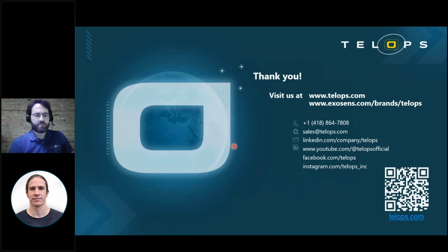Again, if I could read the question, maybe I'll have a different answer. Yeah, it does literally say, how often do you reckon that recalibration needs to take place? The newer upcoming systems will have a different way they're calibrated, and it will be done with that more permanent calibration at Telops. So that's going to be a different method of operating. So you don't need to recalibrate in the field, basically, with those newer systems.